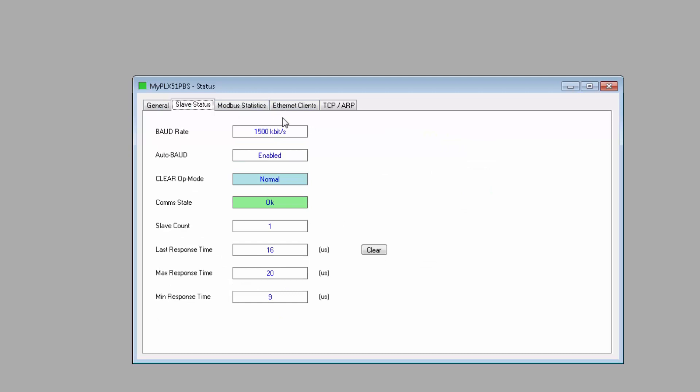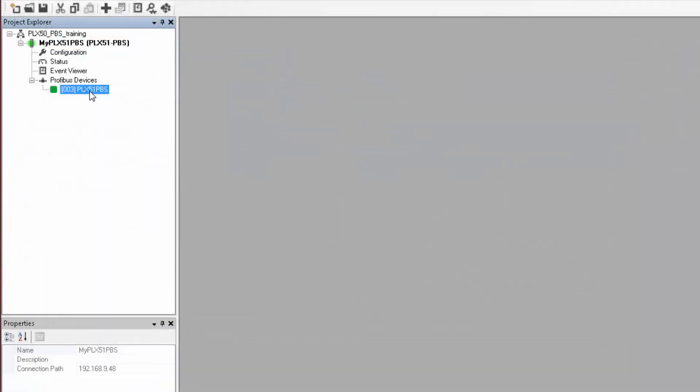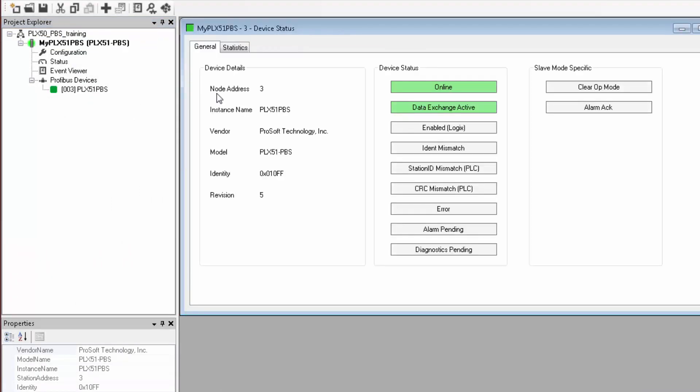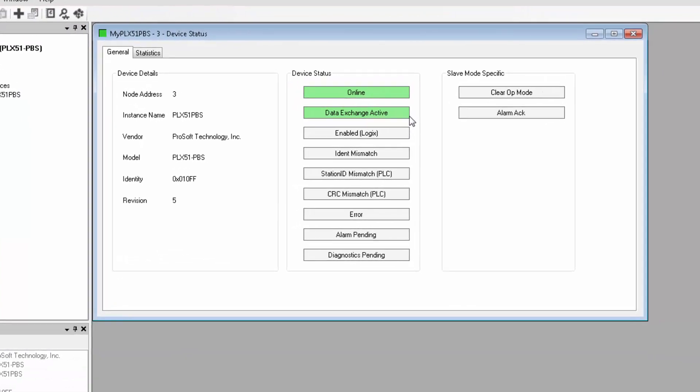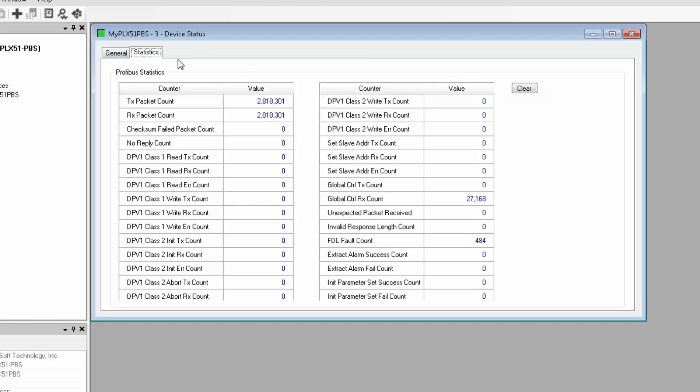Under the slave status tab, you can see the comm state, which indicates a connection to the PROFIBUS master, as well as communication stats. The PROFIBUS slave devices status can also be monitored by right-clicking on the device and selecting the status menu item. This is very handy if you're troubleshooting a device that's not appearing on the network. You can just open this up and see if it's online, is it exchanging data, is it enabled in the PLC program, along with several other flags that alert you to specific problems.